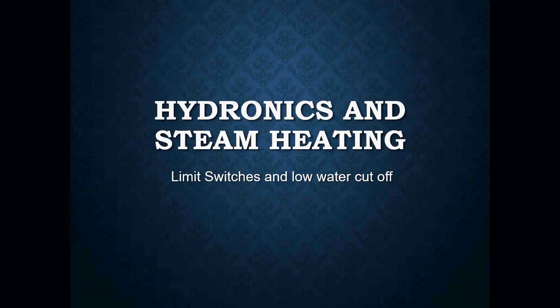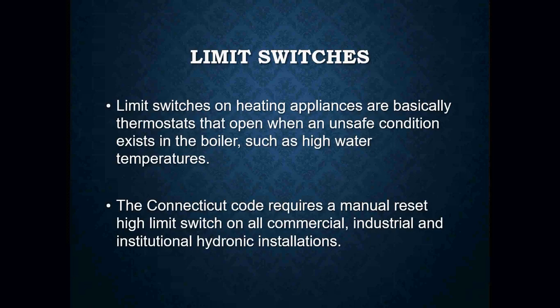Today in this lesson we're going to discuss some of the safeties and low water cutoffs that can be found on a lot of your hydronic and steam heating systems. Per codes — International Mechanical Code, International Residential Code — a boiler has to have a low water cutoff and some sort of safety installed on it in the event of an emergency situation.